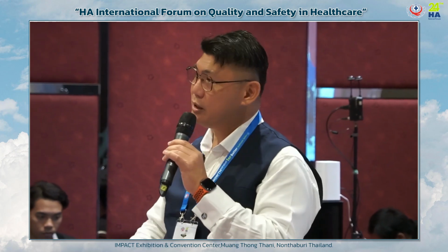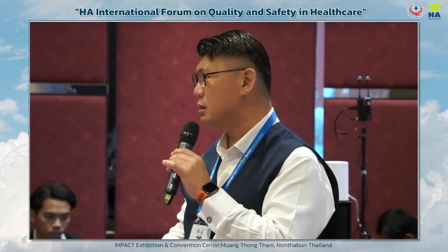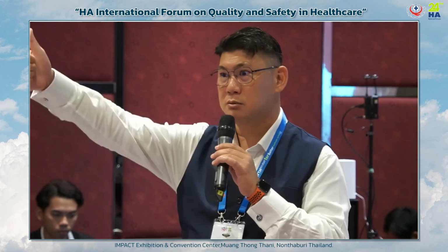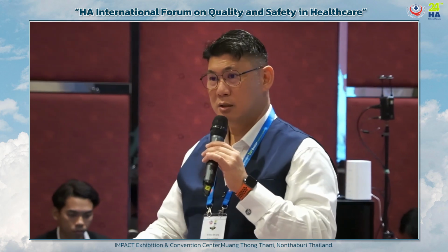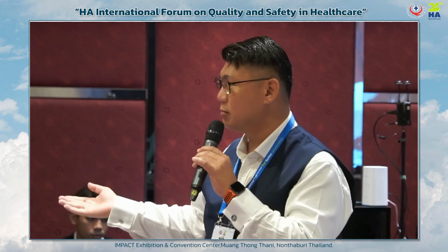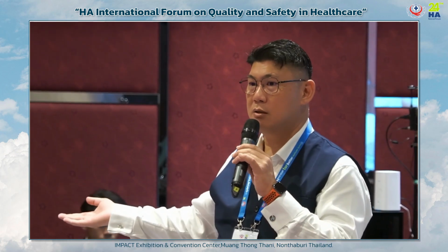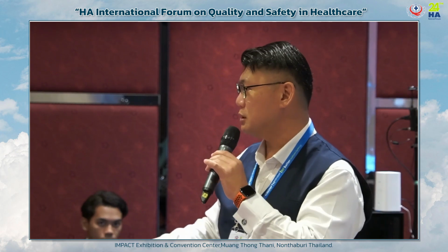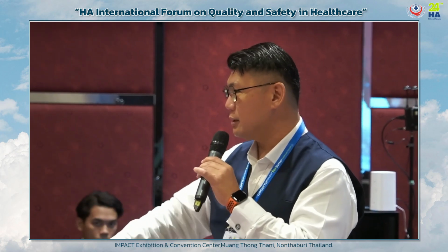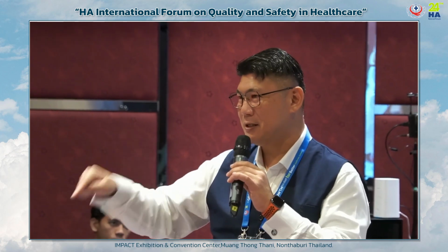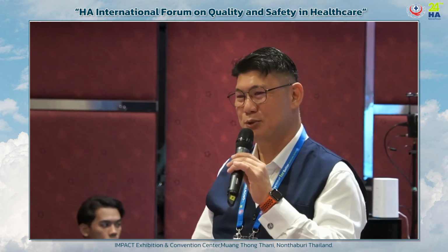Now, when you say the machine is no good, then the next question is, why is the machine no good? Who is supposed to make sure the machine is good? That's the next question. Oh, because we never have a biomedical engineer and we don't have a technician. So nobody fixes the machine. We just use an alcohol wipe, clean, press the reset button, and then press the daily prime button. Okay, I'm good for the analyzer.